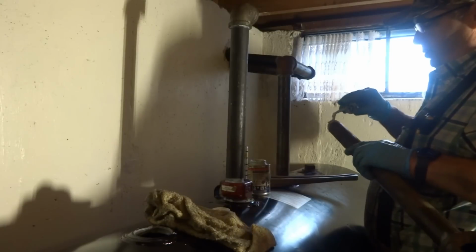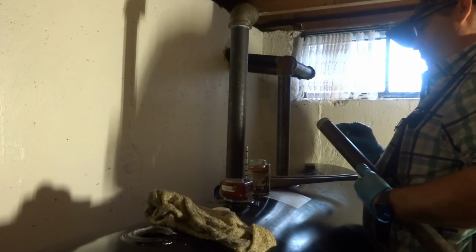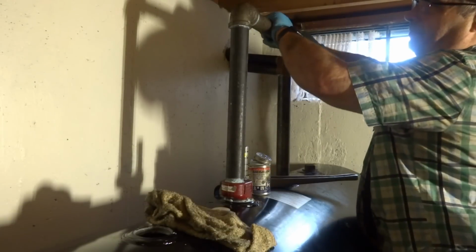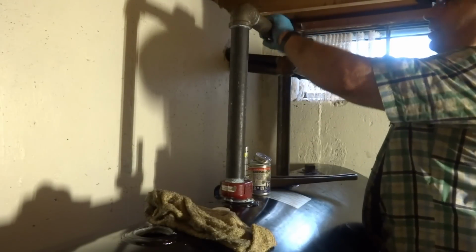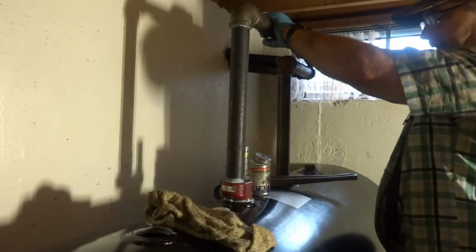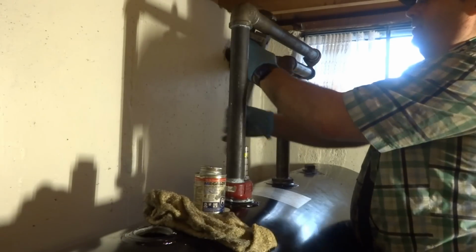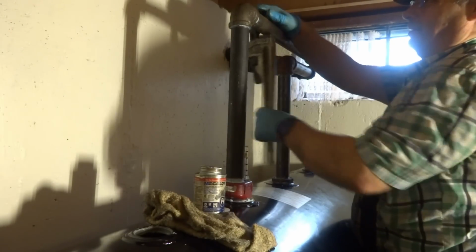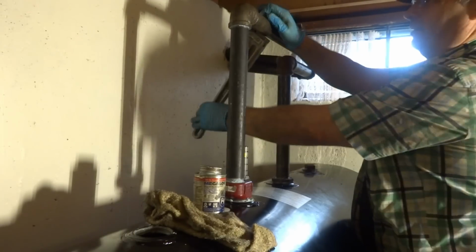This is one of those Roth tanks, so it's got to be inch and a half. Something to do with the pressure on a tank or something like that with the smaller line. They recommend inch and a half on the Roth tanks. I see. We don't have a Roth tank here. Good.